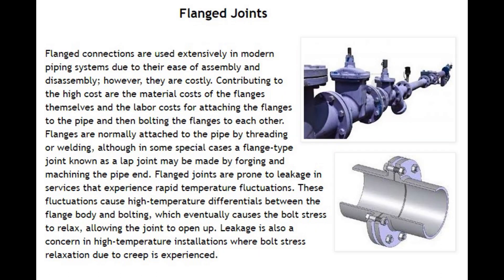Number 6: Flanged Joints. Flanged connections are used extensively in modern piping systems due to their ease of assembly and disassembly; however, they are costly. Contributing to the high cost are the material costs of the flanges themselves and the labor costs for attaching the flanges to the pipe and then bolting the flanges to each other. Flanges are normally attached to the pipe by threading or welding, although in some special cases a flange type joint known as a lap joint may be made by forging and machining the pipe end.